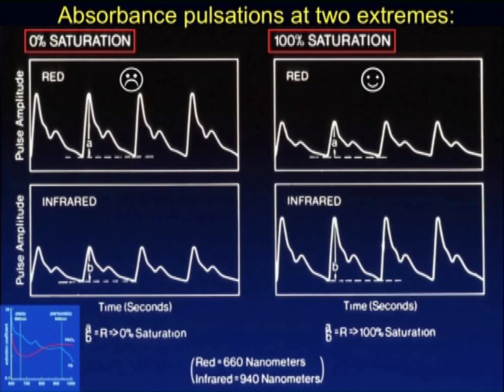The final step, how do you relate that ratio to the oxyhemoglobin saturation, or what we call SpO2? 2 wavelengths in conventional oximeters, pulse oximeters, tend to be around 660 and 940 nanometers. They measure first the ratio of the AC component, which is the fluctuating component, to the DC component at the red, and do the same ratio at the infrared. So now you got 2 ratios, a red one and an infrared one. What do you do next? You have 2 ratios. Well, let's take the ratio. And that's why this is often called the ratio of ratios, or red over infrared. So it's AC over DC red divided by AC over DC infrared. That is the number that's going to be related to the oxygen saturation in the arterial blood.